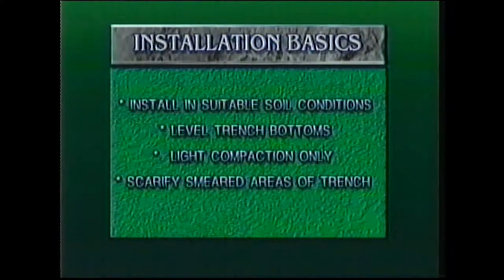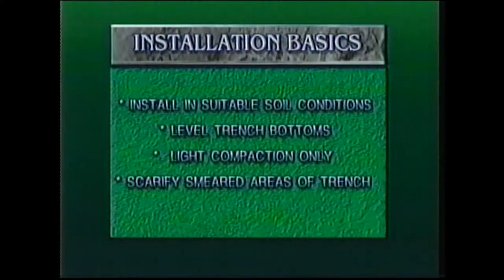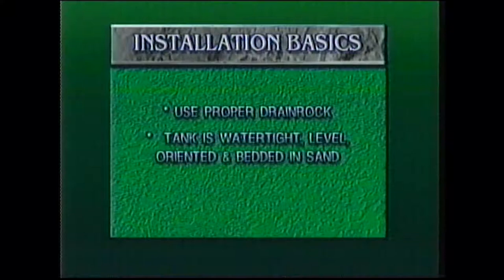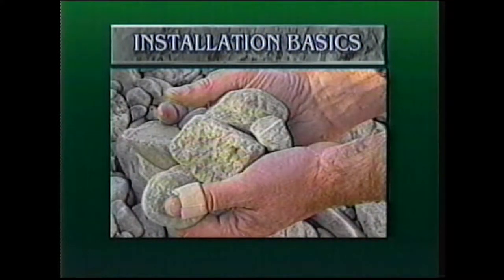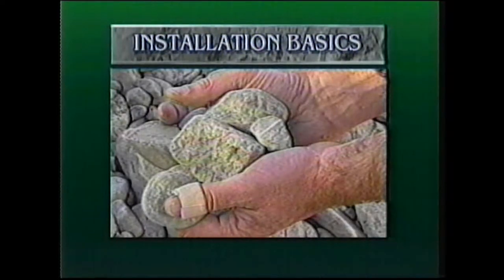There are a few basic things you need to know when installing your system. Install only when soil conditions are suitable and ensure your trench bottoms are level. Do not compact the backfill soil. Do not leave sidewalls of trenches smeared, as this reduces the ability of the soil to absorb liquid. Both the bottom and the sides of the trench can be scarified with a rake. Use proper drain rock — drain rock provides for dispersion of liquids, aeration and protection of the pipes. Drain rock should be clean and measure between 20 to 65 millimeters or three quarters to two and a half inches in diameter. Ensure that fine material from the excavation does not get into the drain rock.